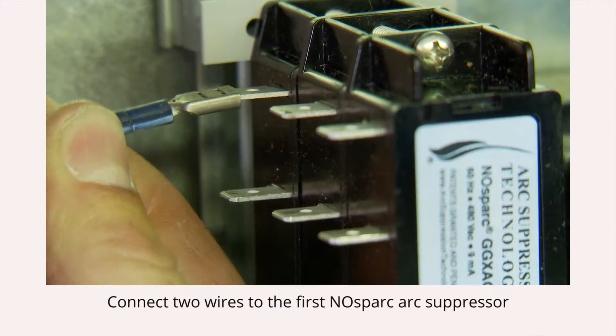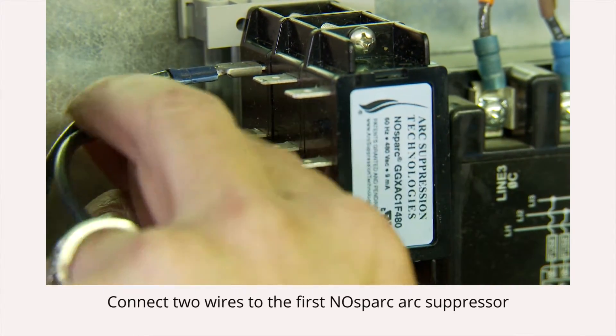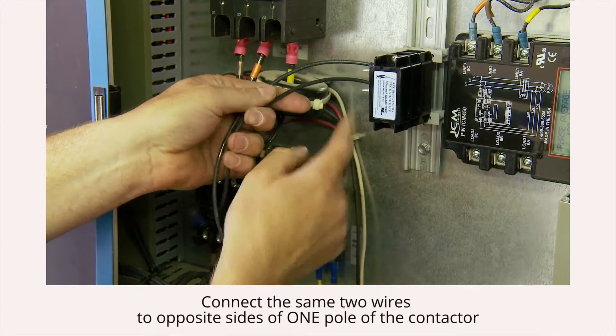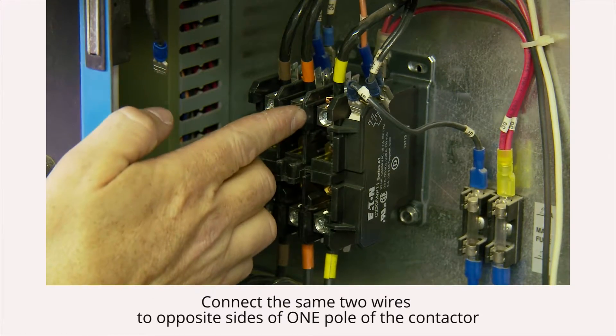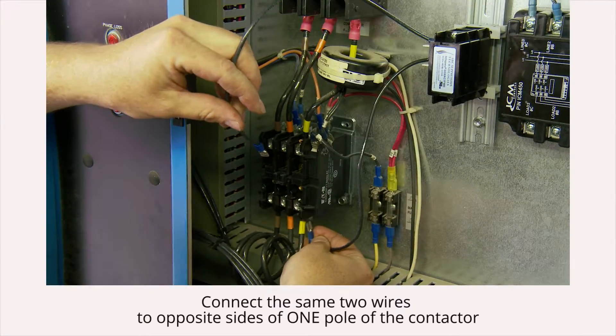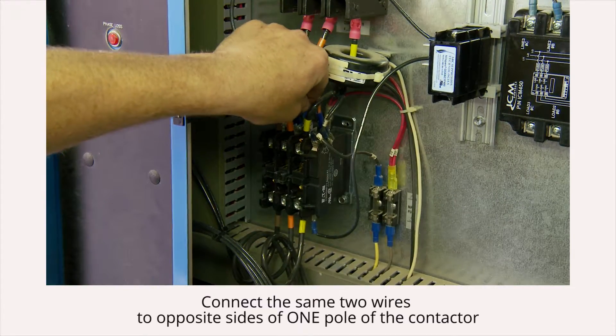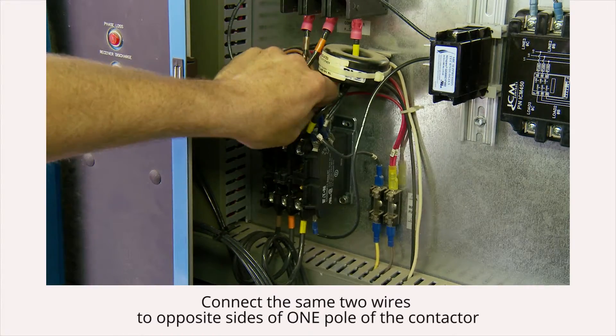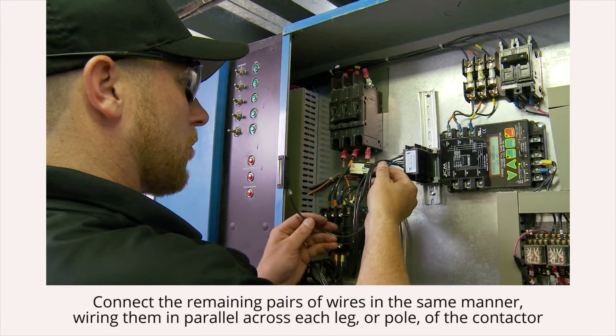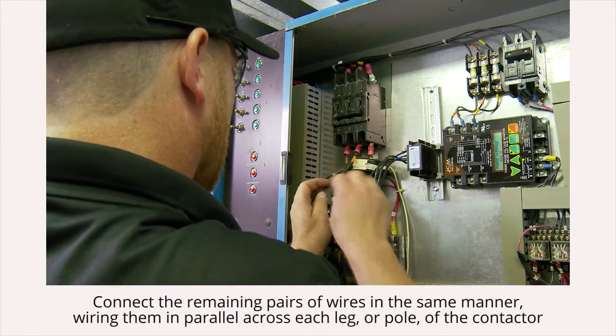Connect two wires to the first NOsparc arc suppressor, then connect the same two wires to opposite sides of one pole of the contactor. Do not attach these wires to different poles. Connect the remaining pairs of wires in the same manner, wiring them in parallel across each leg or pole of the contactor.